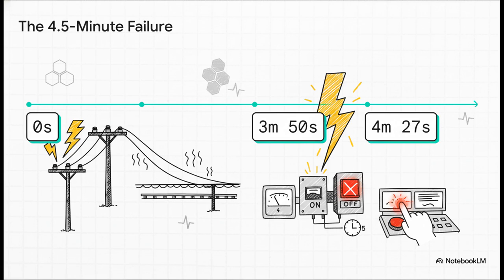This timeline shows how it all played out. The first short circuit happens at time 0. For almost 4 minutes, the lines are getting hotter and hotter, stretching and sagging lower and lower to the ground. Then, at 3 minutes and 50 seconds, they sag so much that they actually touch the overhead power line of the Hansa Line railway. This creates a second, even more severe short circuit. This new, larger current of 15,000 amps was finally big enough to get the attention of that misconfigured feeder protection, which automatically cleared the fault after a total of 4 minutes and 27 seconds. Meanwhile, operators in the control center had figured out what was going on and were manually trying to isolate it, completing their actions just 5 seconds after the system finally tripped itself.